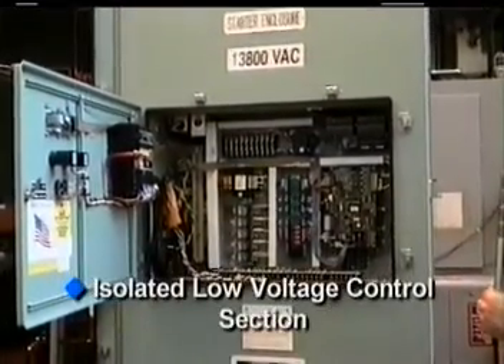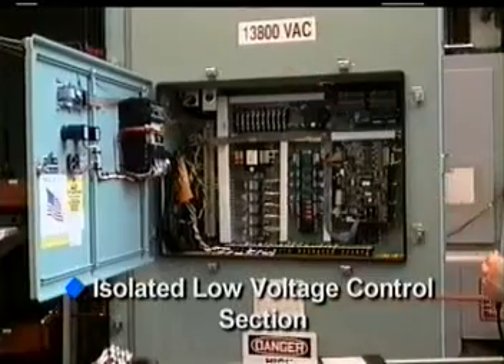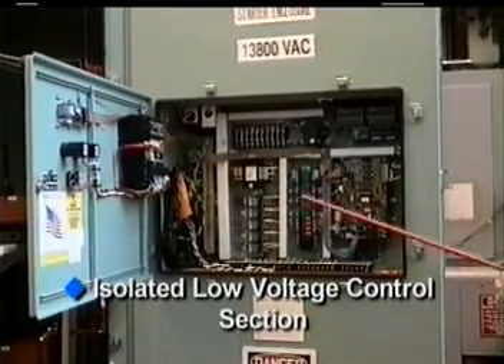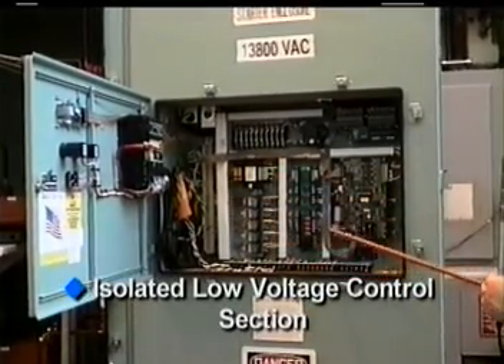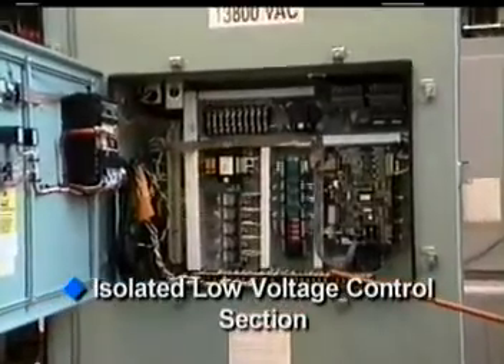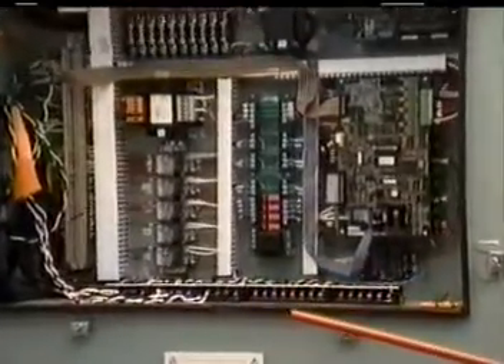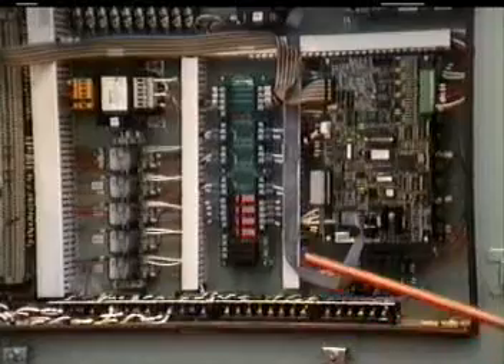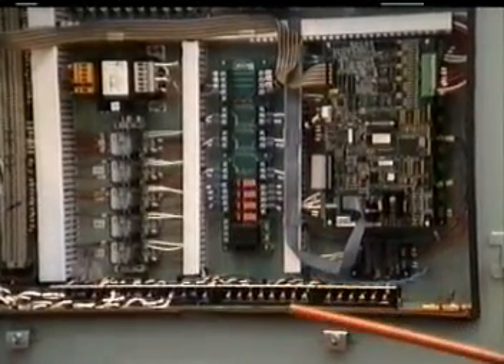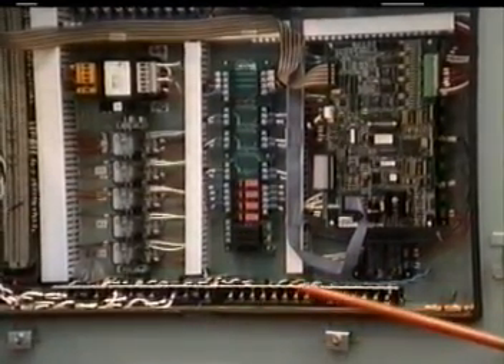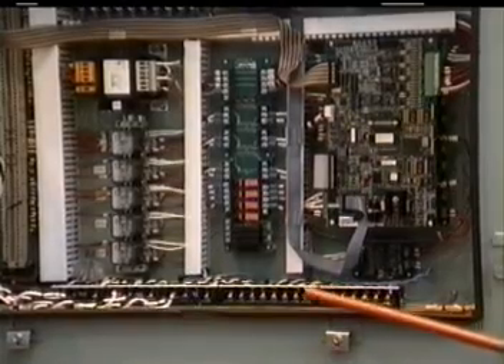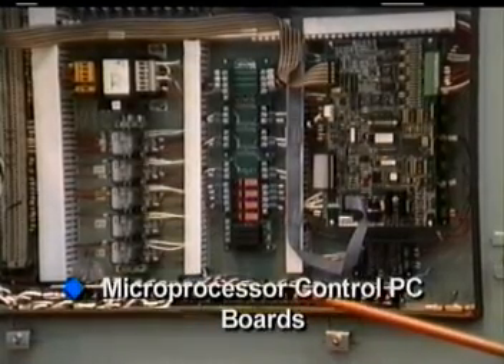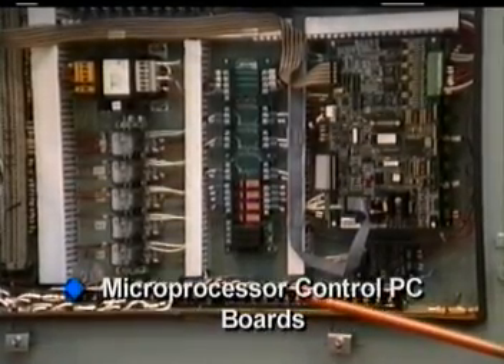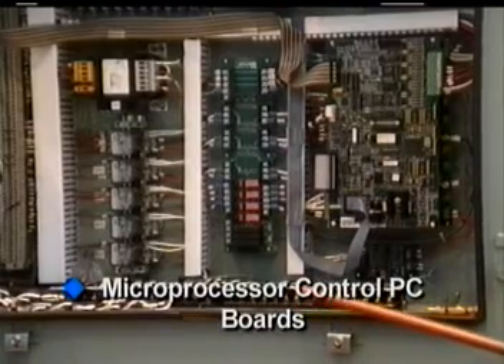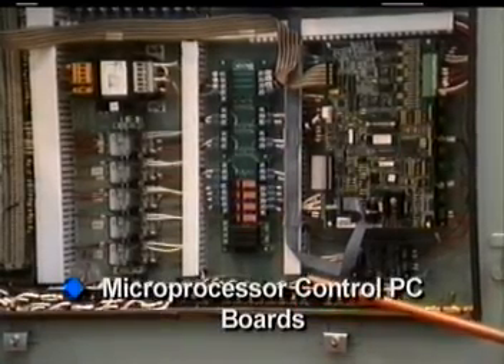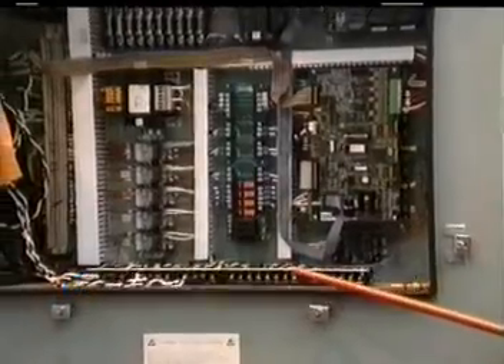Next to the contactor section is the starter solid state section. There is a separate low voltage section within the starter enclosure that houses the microprocessor electronics, which provides the heart of the operation of the system in terms of logic sequence, protection, determination of when to actually gate SCRs on and off, and the control of both the inline and the bypass contactors.